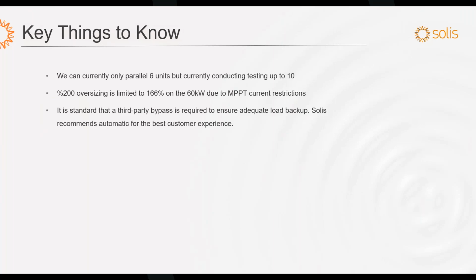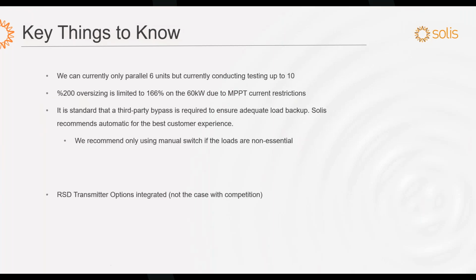There's no bypass integrated into this commercial hybrid. We want customers to know that a third-party bypass is required, especially if you want to ensure adequate load backup. In a commercial use case, like a hospital, this is non-negotiable, especially to ensure the best customer experience. So we recommend an automatic bypass third-party solution. You can utilize a manual bypass switch as well, but that's only recommended if the loads are not essential.